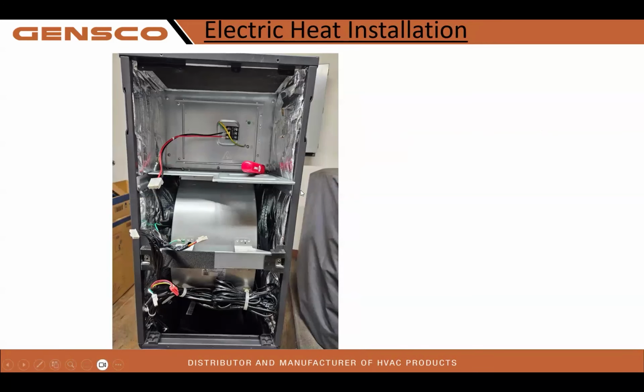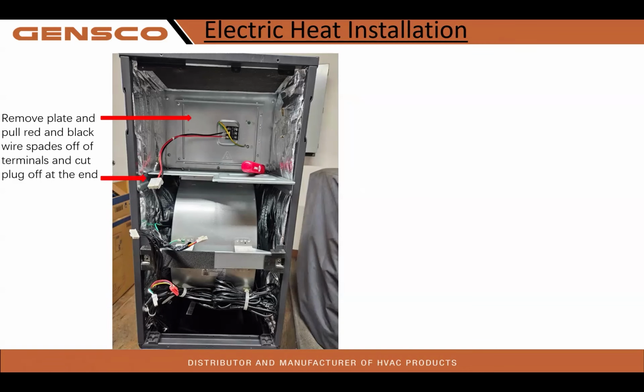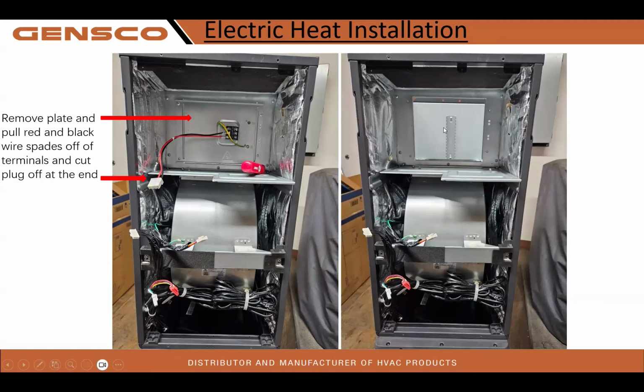There is a look at the control board out of the way. In this illustration, I actually removed the whole board. You will not need to. And notice that plug that plugs into the board and to the back plate. We're merely going to remove that, but we're not going to throw it away. We're going to use that in a later illustration. Remove the back plate. But what we're going to do is cut off this plug. We're going to remove these wires from these stake-on connections, remove those wires, and cut that plug off. We're going to insert our strip heat right here.